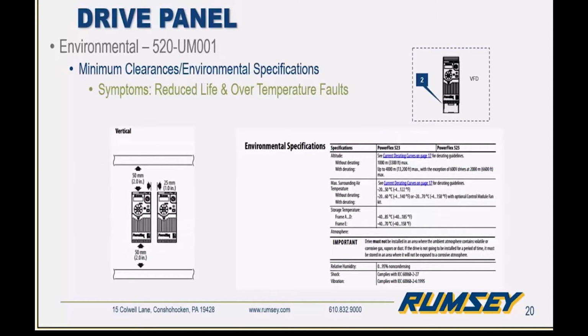So moving on to the drive panel, there are many atmospheric and environmental considerations that need to be made when installing a drive in a panel. I think one of the most common or easily understood is ambient temperature. If the temperature of the air surrounding the drive exceeds its ambient rating, we're going to expect reduced life or over temperature faults to occur, and that's pretty common with any electrical component.